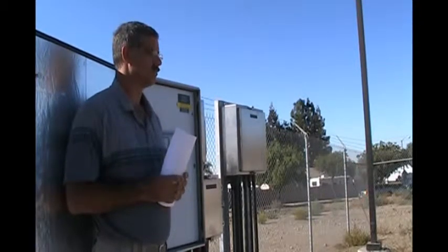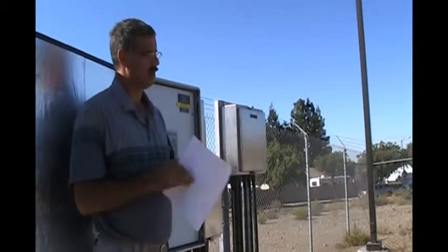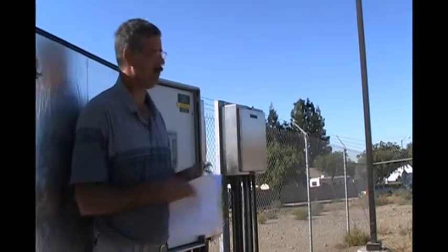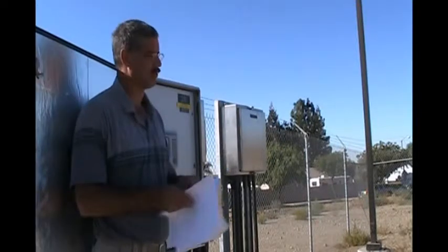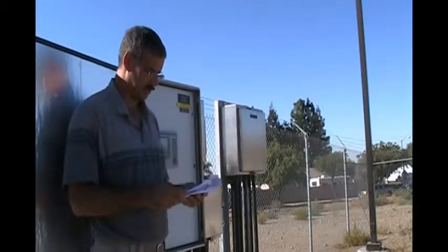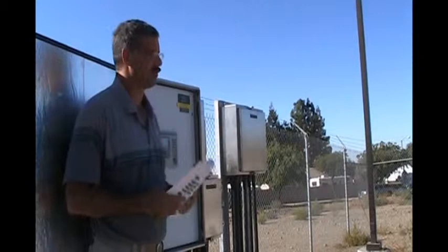There's a dead band. Yeah. It won't. There's a dead band. I don't know what the set is, but if it goes from 13.10 to 13.20, no, it will not adjust the valve. Oh yeah, no. Valve flow rate, dead band percentage. Yeah. It's right in there. To 11. That's your set point in screen number 2. Exactly. That's now I understand the question. Yep. So there's 2% dead band in there.